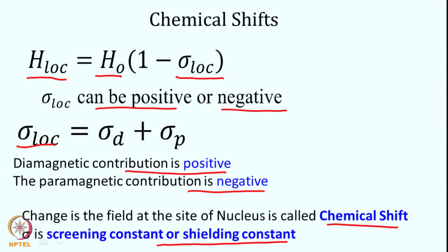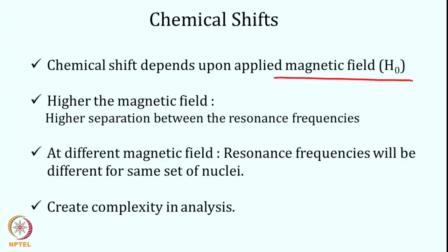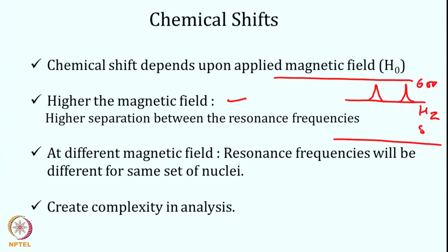The chemical shift depends upon the applied magnetic field H0. The higher the magnetic field, the higher the separation between resonance frequencies. For example, if we record a spectrum at 600 MHz versus 800 MHz, the separation between lines expressed in hertz will be larger at higher field. So higher magnetic fields are better for resolving spectra. However, this creates a problem when expressing resonance frequency in hertz, because at different magnetic fields the resonance frequencies differ for the same set of nuclei.